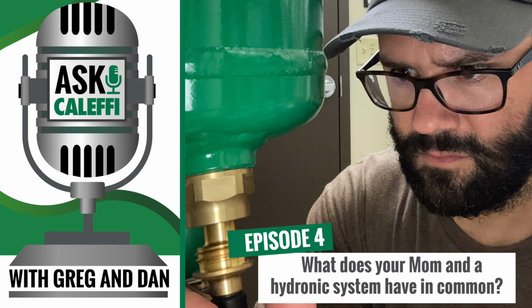Gravity is what's pulling that down, and the fact that the velocity drops so much within that body allows those particles to fall to the bottom. Right. The only product I think we have that it really has an effect on is that rotating collar model, the NA5465. That one with the poly body has an in and an out. It does. And well, that's a vertical device. It's a vertical, but it can be turned as a horizontal too if you've got a really small system.